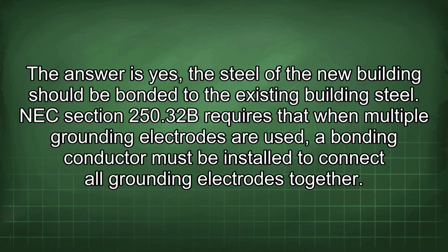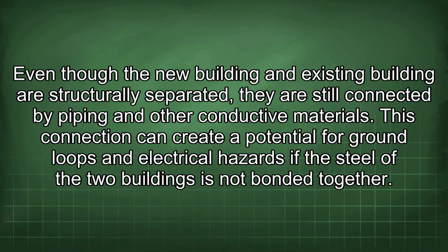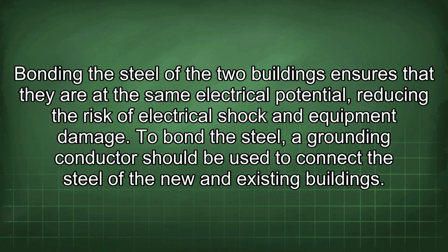steel. NEC Section 250.32b requires that when multiple grounding electrodes are used, a bonding conductor must be installed to connect all grounding electrodes together. Even though the new building and existing building are structurally separated, they are still connected by piping and other conductive materials. This connection can create potential for ground loops and electrical hazards if the steel of the two buildings is not bonded together. Bonding the steel of the two buildings ensures that they are at the same electrical potential, reducing the risk of electrical shock and equipment damage.